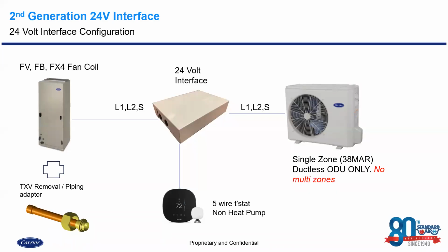So with the FV, the FB, and the FX fan coils you'll see on here, this is what you're going to need to make this setup work. You're going to need a 38MAR single zone outdoor unit only, no multi-zones as it stands right now. We're going to need a 24-volt interface. We're going to need a 5-wire non-heat pump thermostat, so we need one that's programmable as a one heat, one cool. Of course, we're going to need our applicable FV, FB, or FX fan coil.